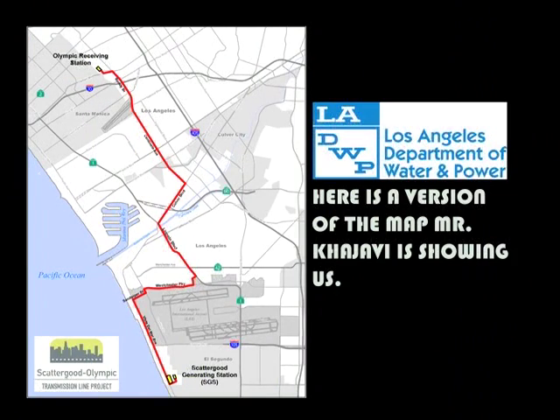What I do is head a group of engineers who design and maintain underground transmission. The process of design started over a year ago, and we're in the process of building the conduit. First we build conduit, fill the conduit, then pull cables, splice, and install maintenance holes — all coming up in the next two years. Now, you've got this map behind us. What's the significance of this map? This is an aerial view showing the route — this purple line.